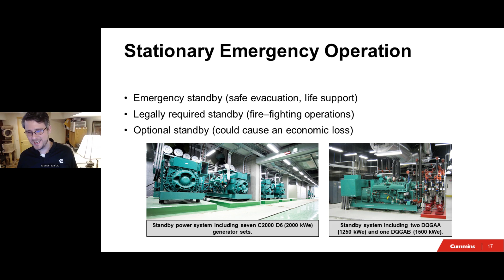There are still some restrictions as part of that. One, during an emergency, there's unlimited operations, maybe not a restriction, the opposite. So during an emergency situation, an emergency generator set can operate indefinitely, no limitation to its usage per the EPA. Outside of that, you get 100 hours and 100 hours only, and that's really intended for maintenance and testing. That is the purpose of those 100 hours.